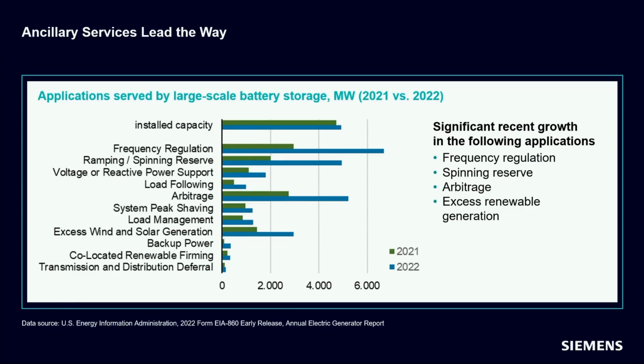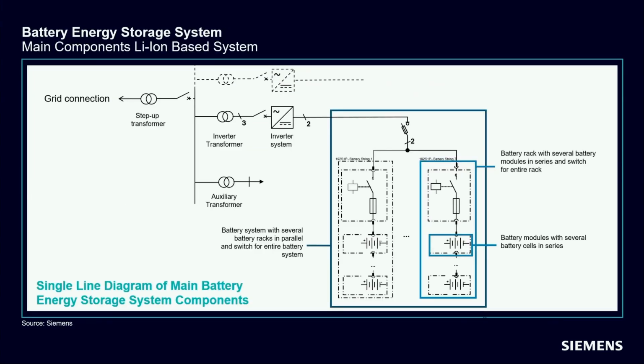Let's very quickly look at some of the major components for a utility-scale BESS system. These are presented in the single-line diagram here. First, on the DC side, behind the inverter, there will be the complete battery system comprising battery racks and battery modules with cells connected in series. This battery system is connected to the inverter, where conversions from DC to AC takes place. Inverter transformers from all the arrays are then connected to a common medium voltage busbar. The voltage is further stepped up with a step-up transformer and connected at the interconnection point to a public grid.